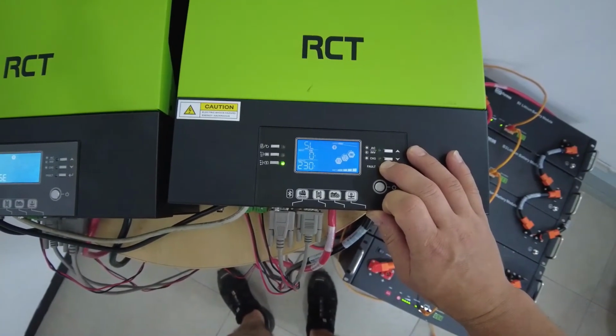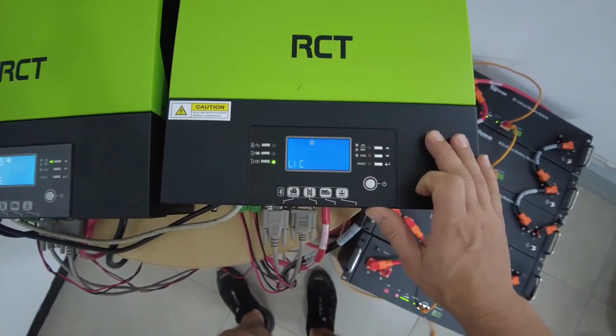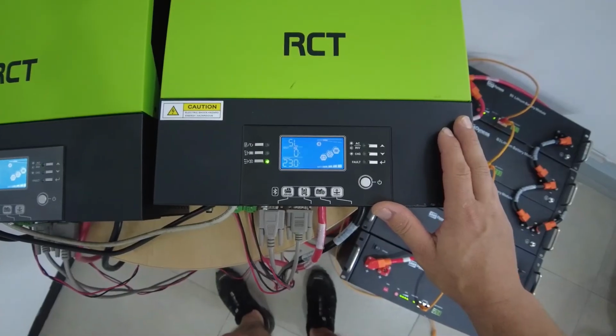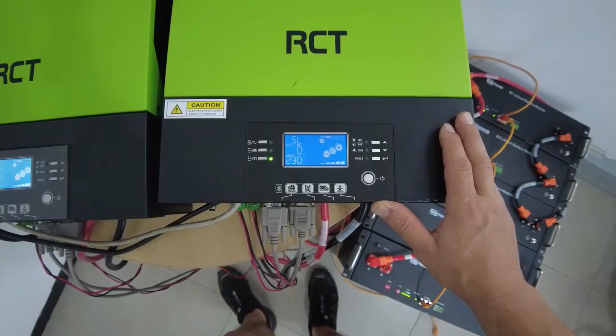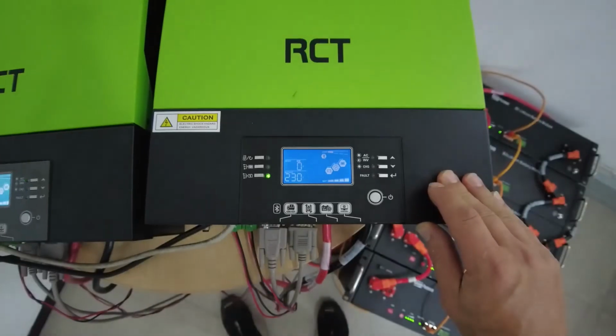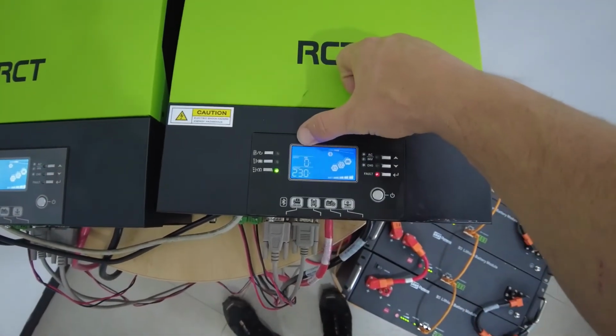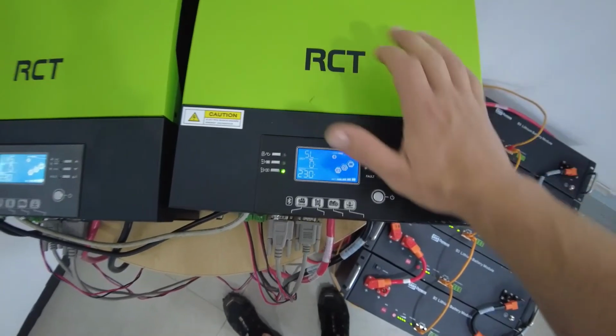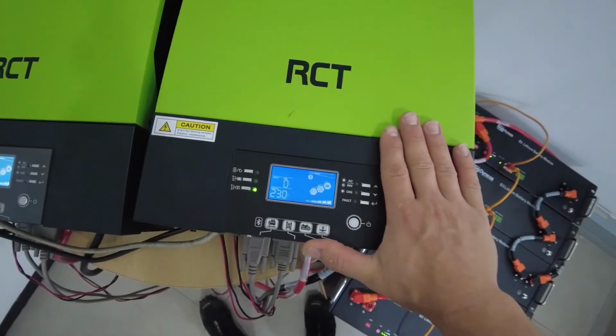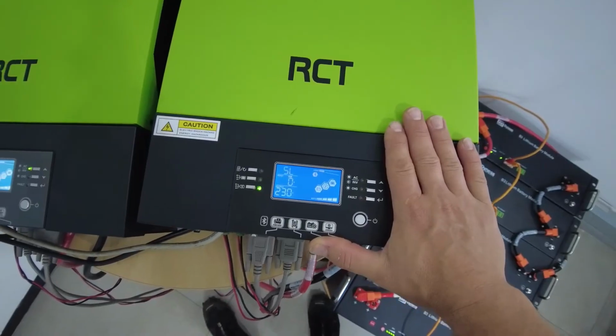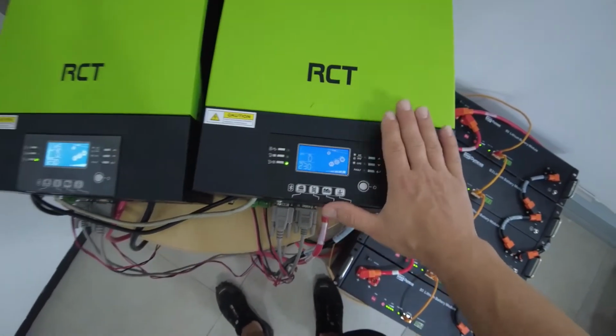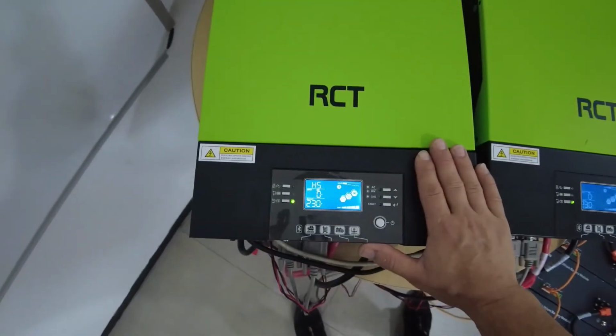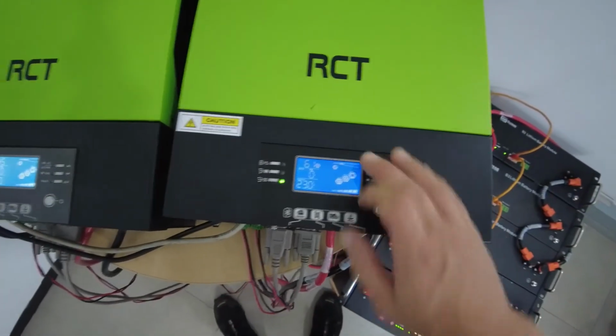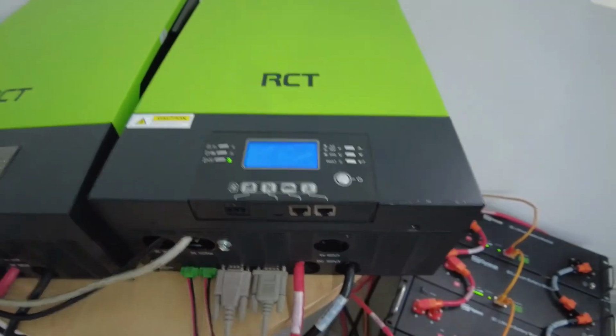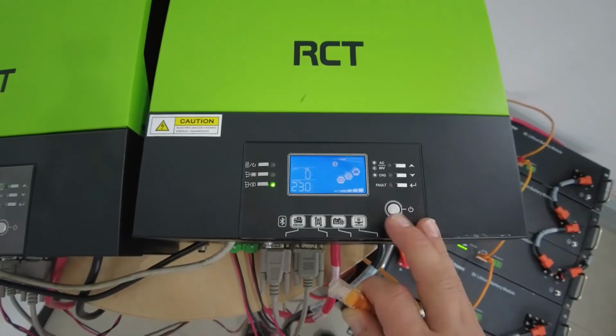This one, as mentioned, we leave on LIC to communicate with the batteries. So currently just waiting for the 61 warning to pop up to establish communication. There we go. 61 warning. Now, as mentioned, you can see this is your slave inverter, but because we've set the inverter to our right as the inverter connected to the battery, set it on battery type number setting 5 to LIC. This is the inverter currently looking for the BMS communication. This is not still on master. It's not giving you any warning at this stage. 61 warning, it tells you there's no communication. It's because I've deliberately disconnected the BMS connector to show you this setup.